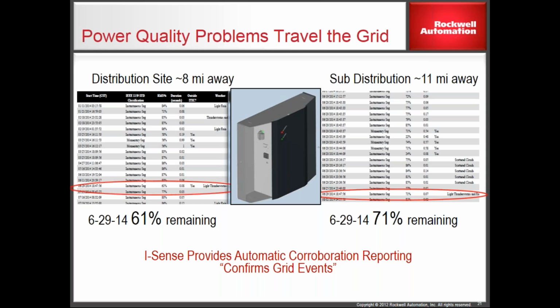In this case, the monitors are about 20 miles apart from each other. In one case, we see a sub-distribution level with an event that took place on June 29th. It dropped to 71% remaining voltage at that site. While at the same time, 20 miles away, at another site being fed at a distribution level - when I say sub-distribution, I'm talking neighborhood level, 12.8, 13.2. At a distribution site, we're looking at maybe 47 kV, 69, it could be as high as 139 like some of the auto plants, but you're up here high on the grid.